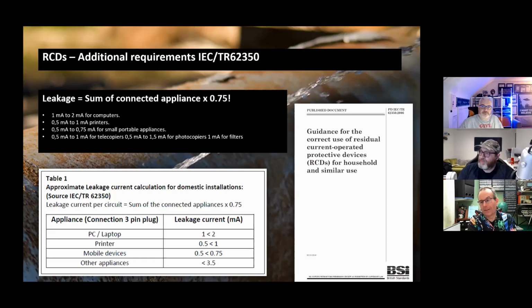Is that a maximum permitted leakage allowance for the standard? Is that what those are? Yeah, it's a maximum permitted, and then some are things like so many milliamps per kilowatt of connected load, and some don't even have one once it goes over a value. We looked at this the other day, John, didn't we? Electric cookers were a maximum of 10 milliamp, which straight away warrants a dedicated circuit. Yeah. So, you know, they're electronic, they're energy efficient now.